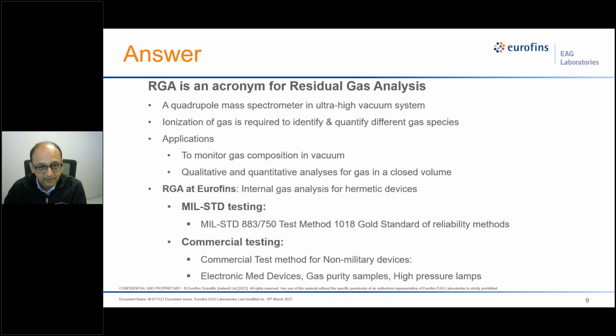Now, the main mode of analysis here is when you introduce a gas into an ultra-high vacuum chamber, ionization is performed through the mass spectrometer system, and the ions are then measured by the mass spectrometer to first identify as well as quantify the different gas species. Now, what are the major applications? The simplest quadrupole mass spec systems with low resolution are used for monitoring the gas composition in a vacuum system, or where you want to monitor the gas quality.